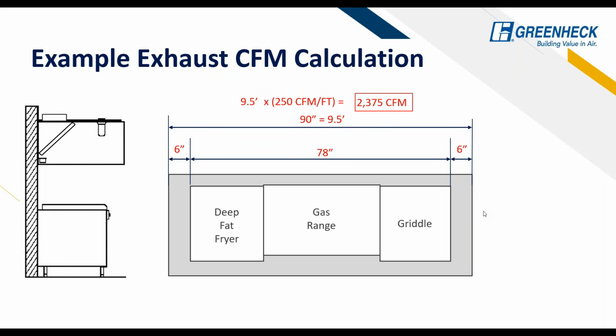Sometimes, when you look at these kitchen hoods, what I see a lot is there's a lot of focus on the BTU ratings and stuff like that. It really doesn't come down to that when you're sizing a hood. All it comes down to is the type of appliance that's being used. Then you look at the heaviest duty appliance and you size the whole hood according to that.